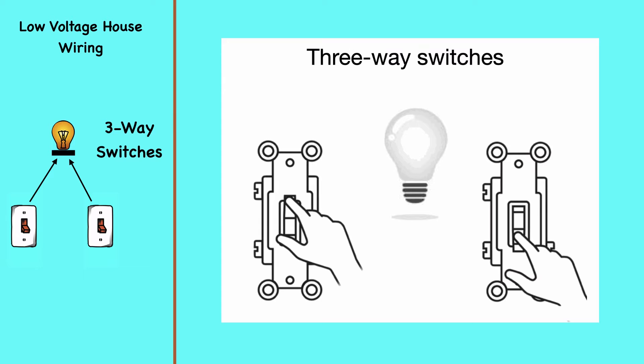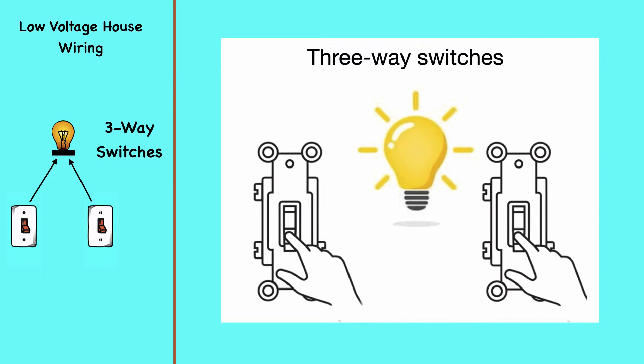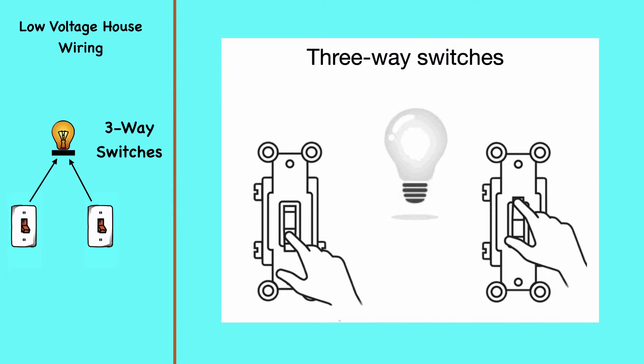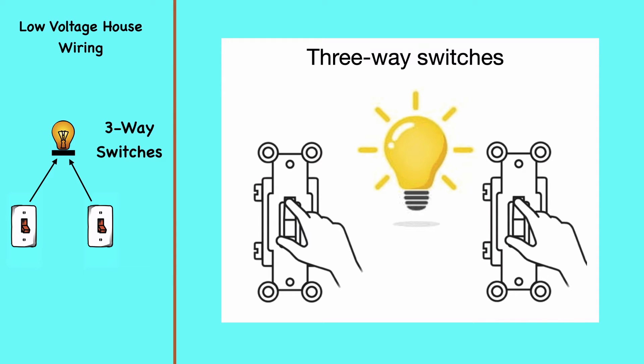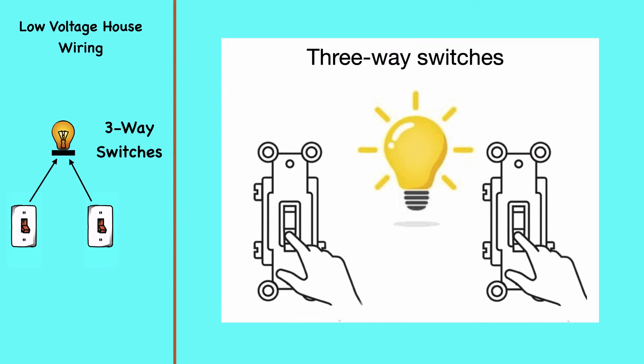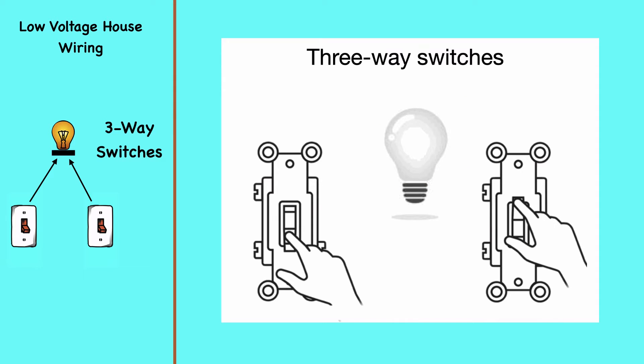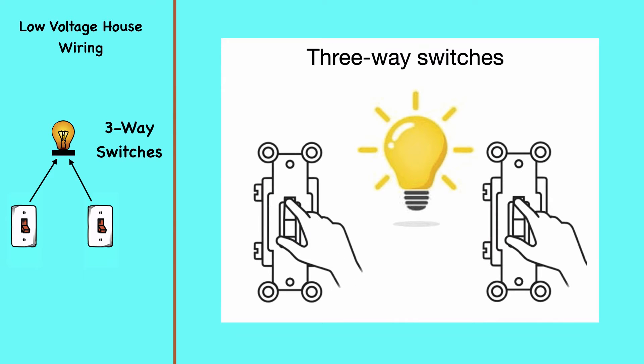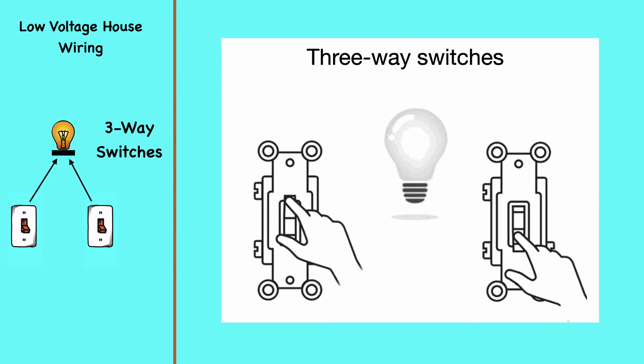Depending on the manufacturer, the travelers may be on opposite sides of the device, or the two terminals may be on the same side. In any case, the common terminal will be distinguished from the travelers in some way. The common terminal will always be connected to a hot wire, either from the source or on the light fixture. These connections can be reversed if it's more convenient, as long as one of the three-way common terminals connects to the hot source and the other connects to the hot on the load — these circuits will work properly.